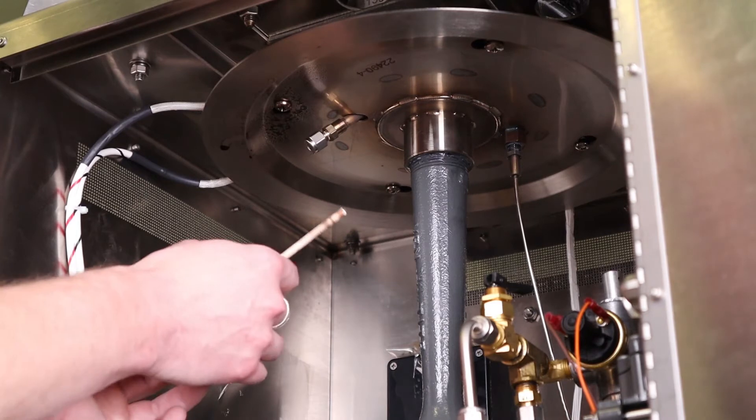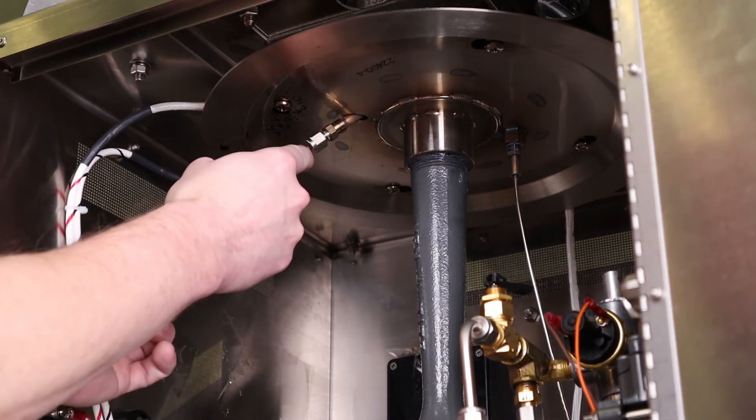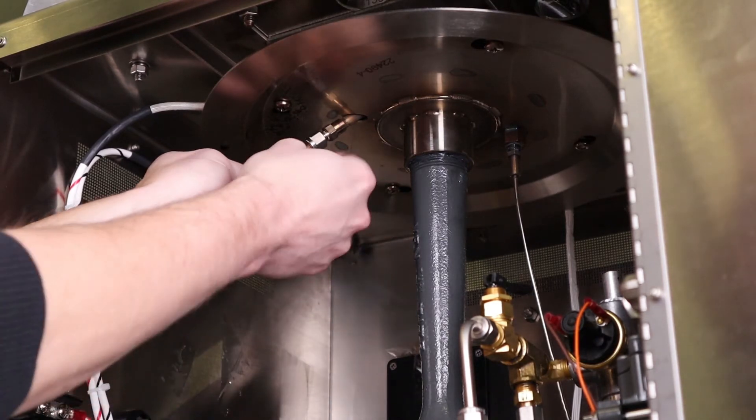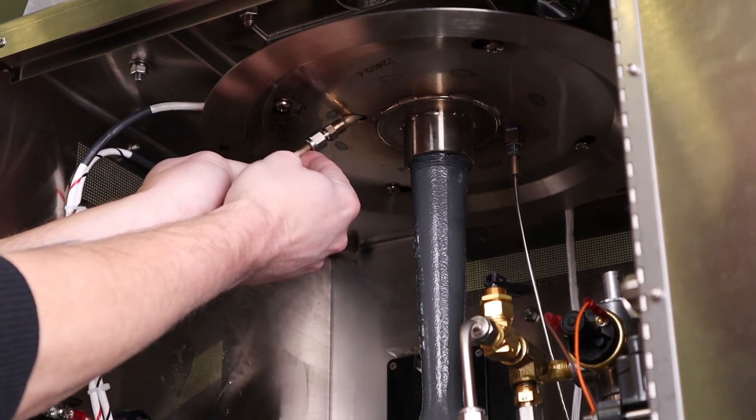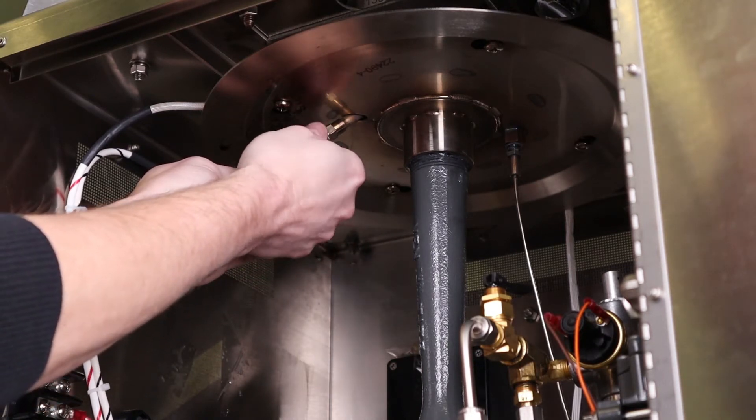Next we're going to install the spark igniter electrode into the fitting on the bottom of the burner. Put it in and slide it all the way in until you feel it bottom out, then pull it back approximately a quarter inch or six millimeters and hand tighten the fitting.